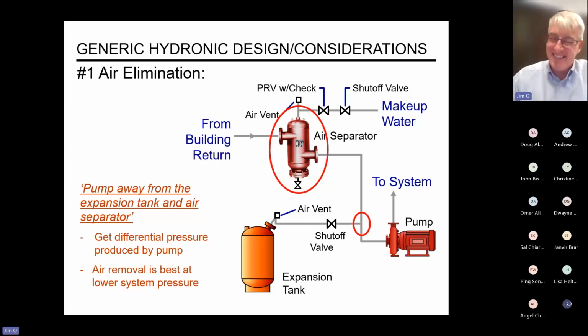And he basically screamed at me, "You pump away from the expansion tank and the air separator." And hence here it is on this piping schematic that I took a long reason to explain. But anyway, the reason you want to have these two devices in this location is that you want to create a differential pressure that's produced by the pump, and also, it's probably more important, air removal or non-condensable removal happens best, or you get the best effect, at the lowest system pressure. And so your lowest system pressure is on the suction side of your distribution pump here.